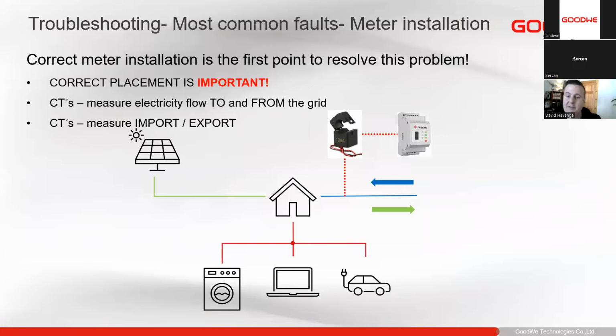All of our hybrid inverters will typically come with the smart meter in the box, so you don't need to purchase anything else. The CT comes with a cable. It's typically around 5 meters. We should not extend that cable. They can be extended. It's not advisable, but maybe 10 or 15 meters maximum. But I wouldn't advise extending your CT cables. The longer the cable, the lower the accuracy, the more loss you have on voltage. So the longer you have that cable, the less accurate your readings are going to be.